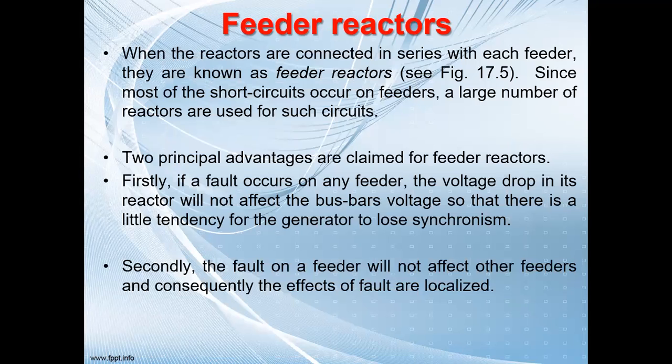Now the feeder reactors, from the name it is clear that they should be connected with the feeder, not with any other parts. It is normally connected in series with the feeder. So when the reactors are connected in series with each feeder, they are known as feeder reactors. Since most short circuits occur on the feeders, a large number of reactors are used for such circuits, because ultimately the loads are connected at the end, and the feeder has to carry that load current. The chances of fault occurring are at the load side.